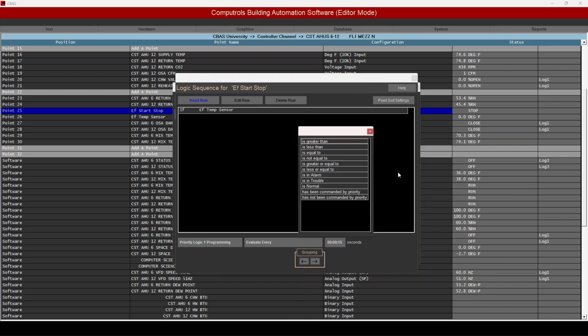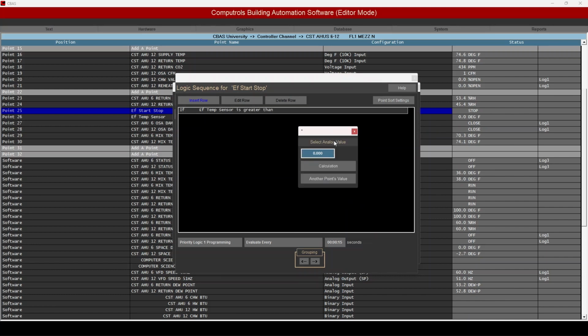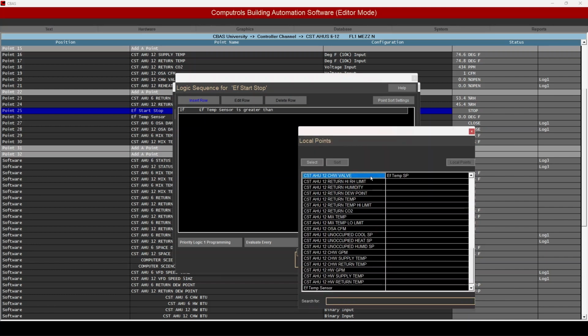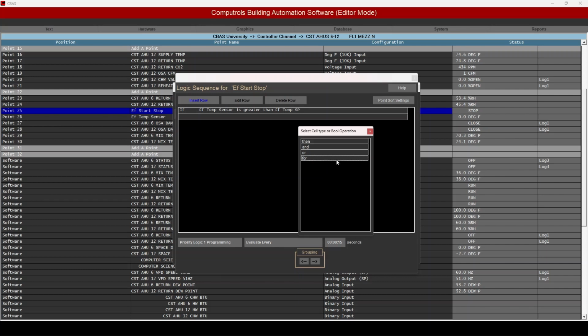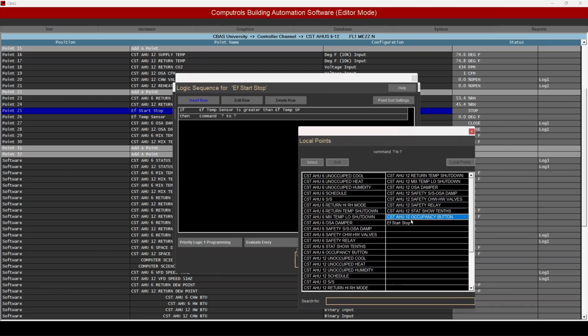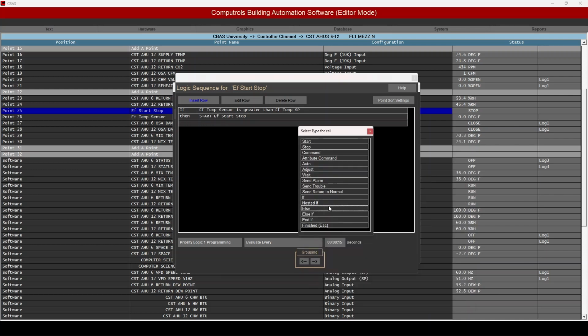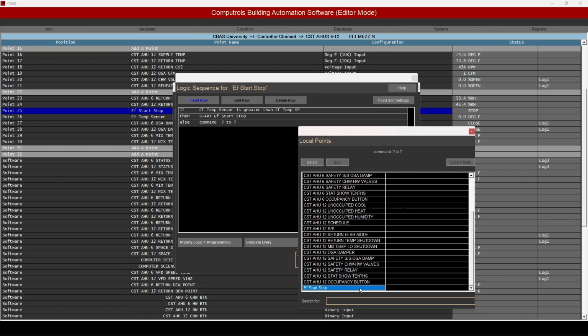If the temp sensor is greater than another point's value, the set point — I could get fancy and say for x amount of minutes, etc. — but I'm just going to say if it's greater than the set point, then start the exhaust fan start-stop. Otherwise, else, stop.